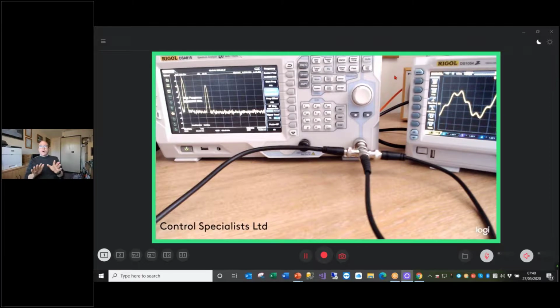So that's the demonstration done. What I wanted to show you primarily out of all this is that when we get anything close to a square wave, the physics behind it emits a very wide range of frequencies, much higher than the fundamental frequency. You may be aware of harmonics on the input side, but those are based on the fundamental frequency of the supply voltage, so we end up with harmonics maybe up to the order of kilohertz. I'm talking here on the output side, between the inverter and the motor, switching on and off very quickly, so we now potentially have currents whizzing around at much higher frequencies.